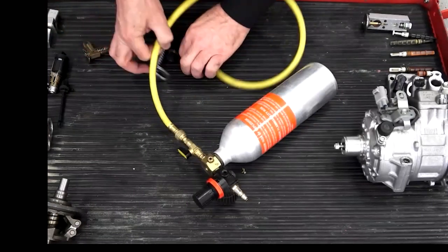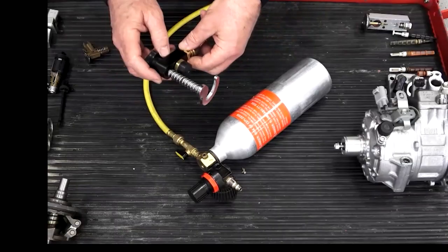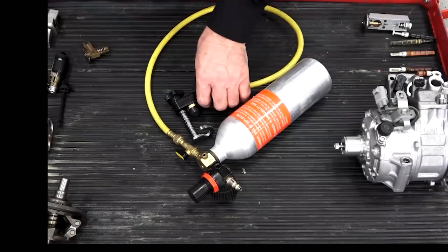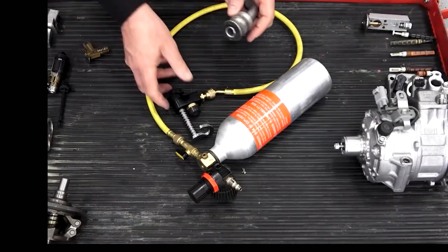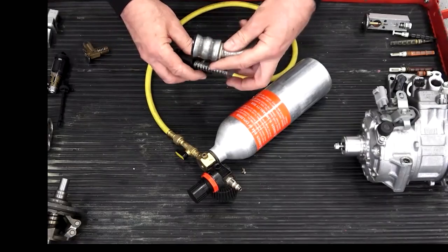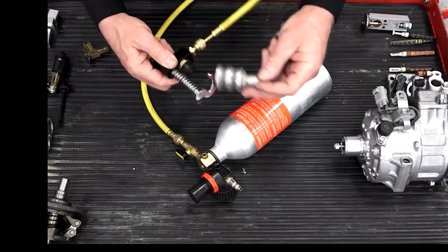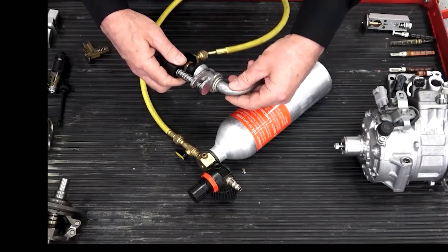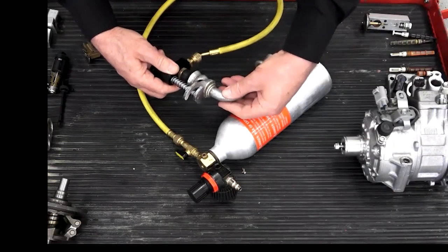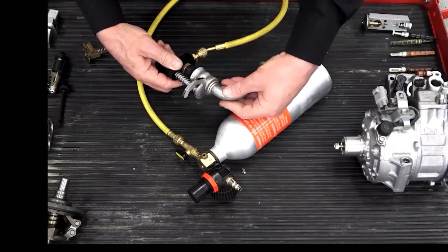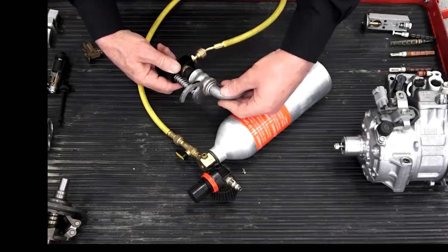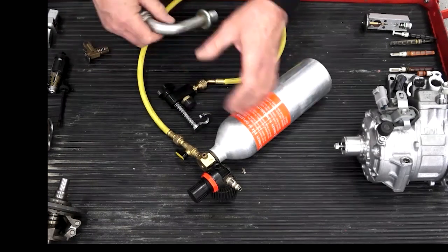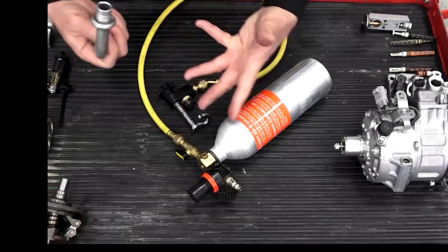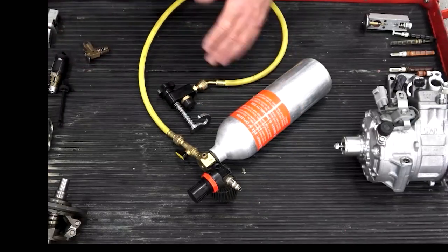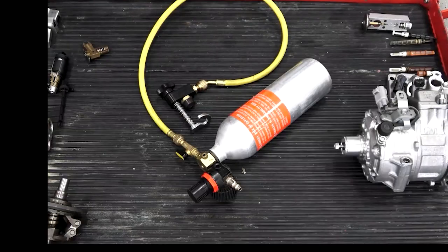And I can walk away because this tool also has a universal adapter. You see this universal coupler here? I've cut it just for demonstration purposes. I can attach this universal adapter to a line or to the evaporator, and it's a permanent attachment. I don't have to stand there holding it, so I can do the flush, then dial the pressure up to 80 psi, walk away, and let the shop air, especially dry shop air, do a powerful job of drying up any residue in the bottom of the evaporator.